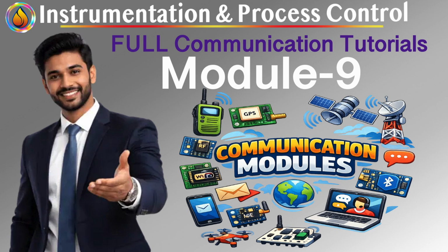Field-level control logic, scheduling, failure impact, and why troubleshooting either feels clean or impossible. This episode is where good architecture quietly proves itself, or betrays you. By now, you understand that function blocks can execute in the field and that communication is scheduled, not opportunistic. What most teams underestimate is how deeply those two facts shape control performance, failure behavior, and how fast a human can reason through a fault. This isn't theory.